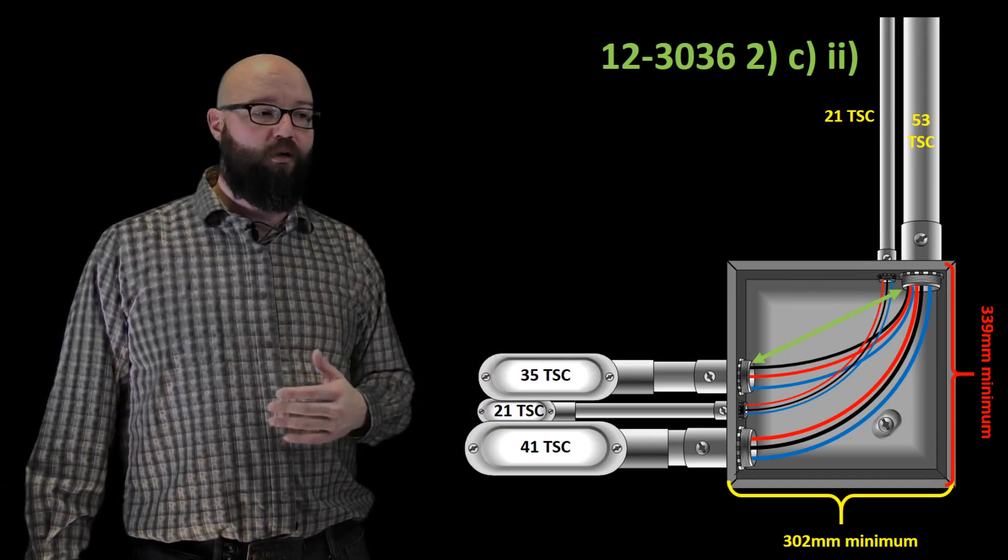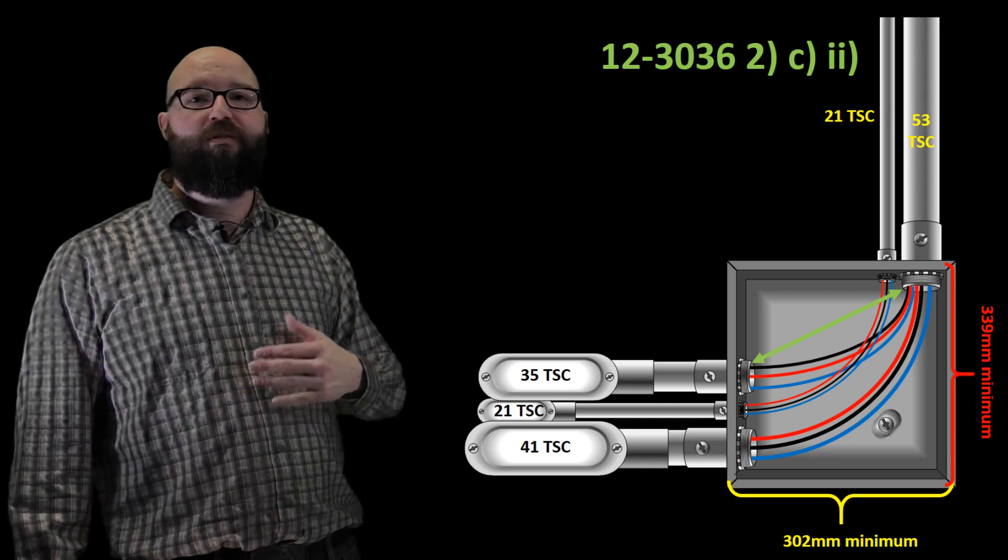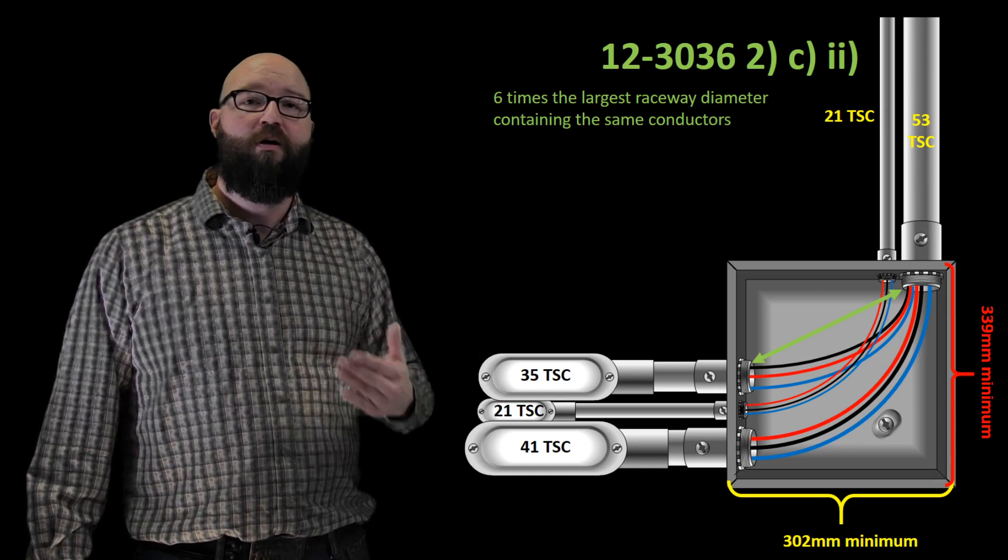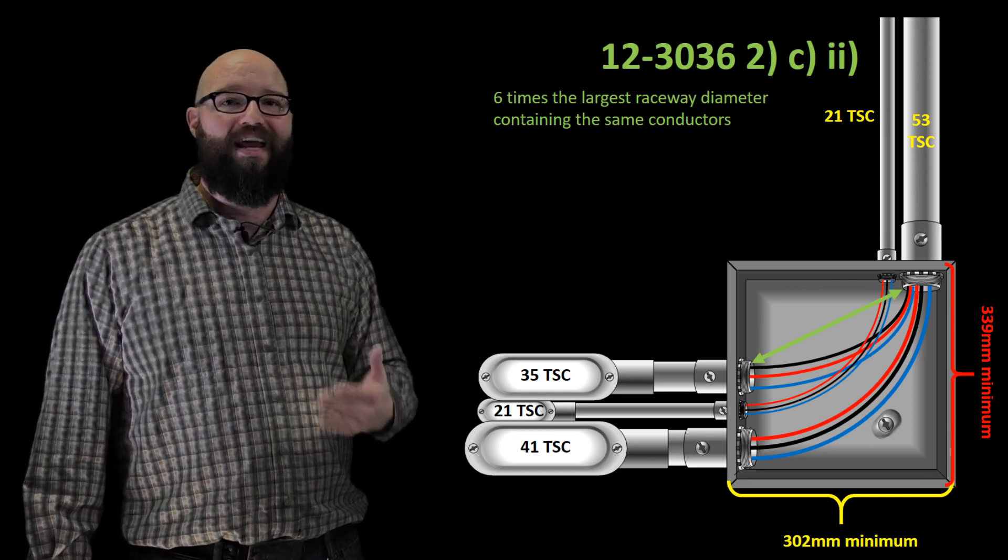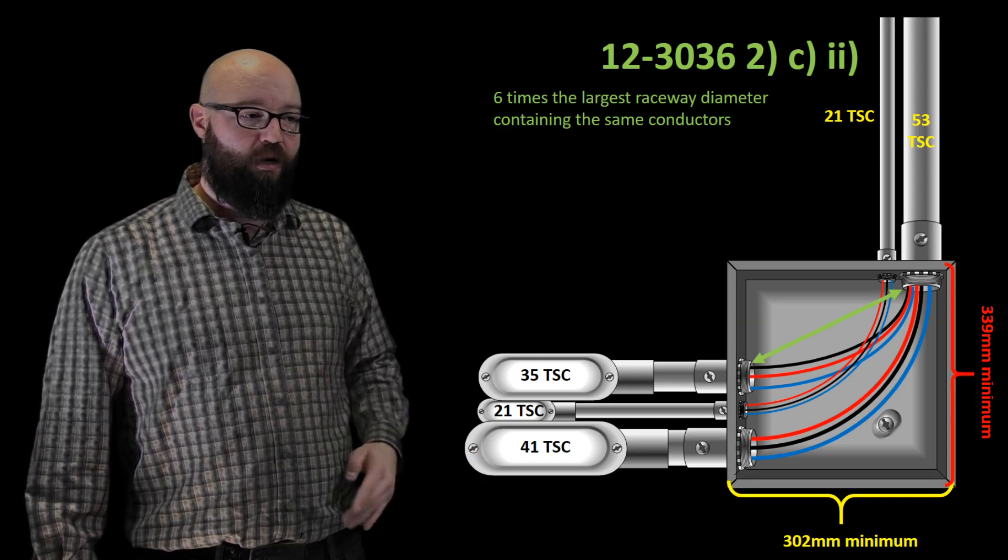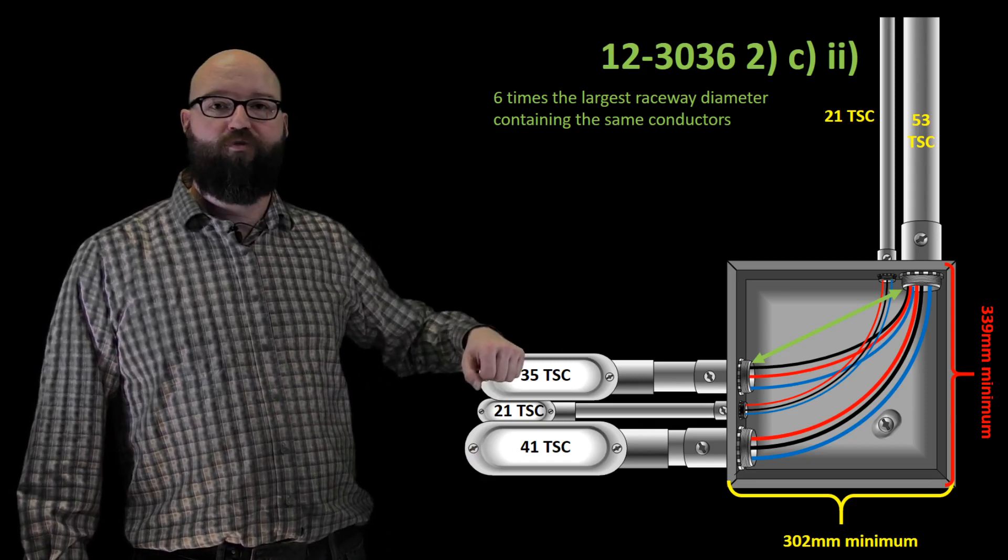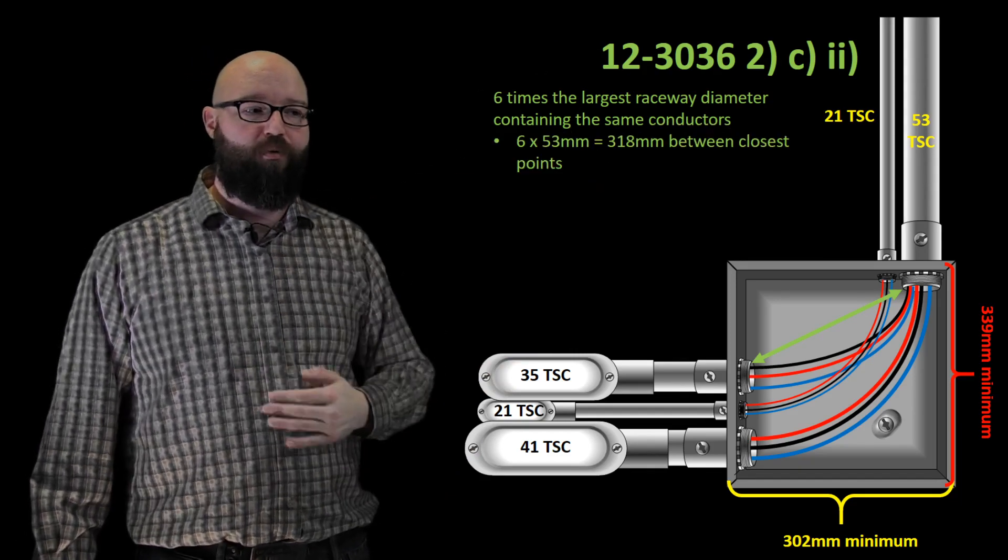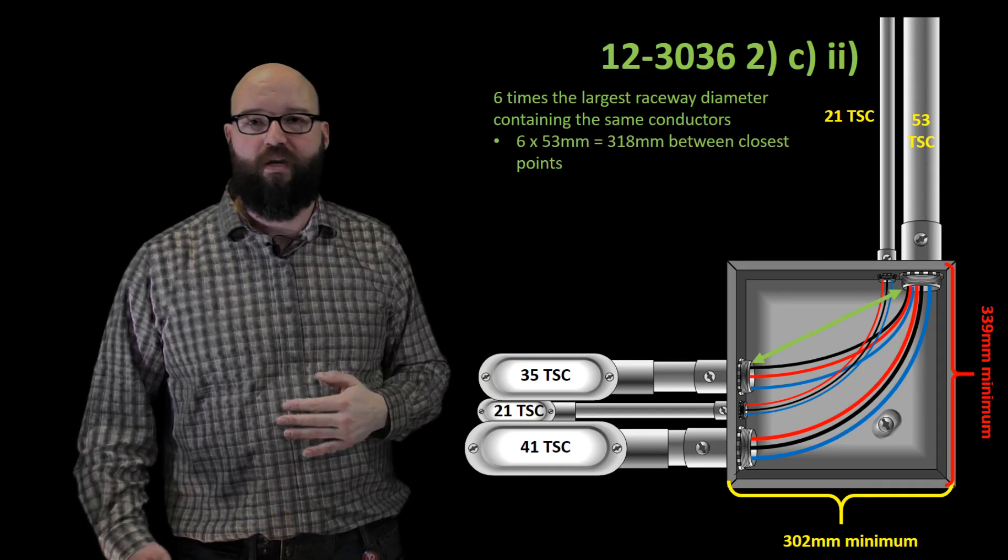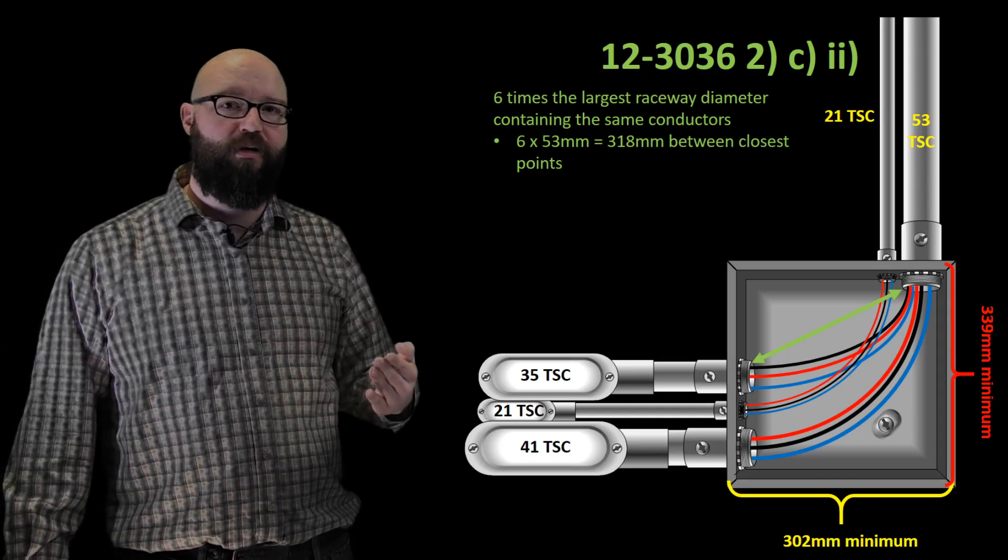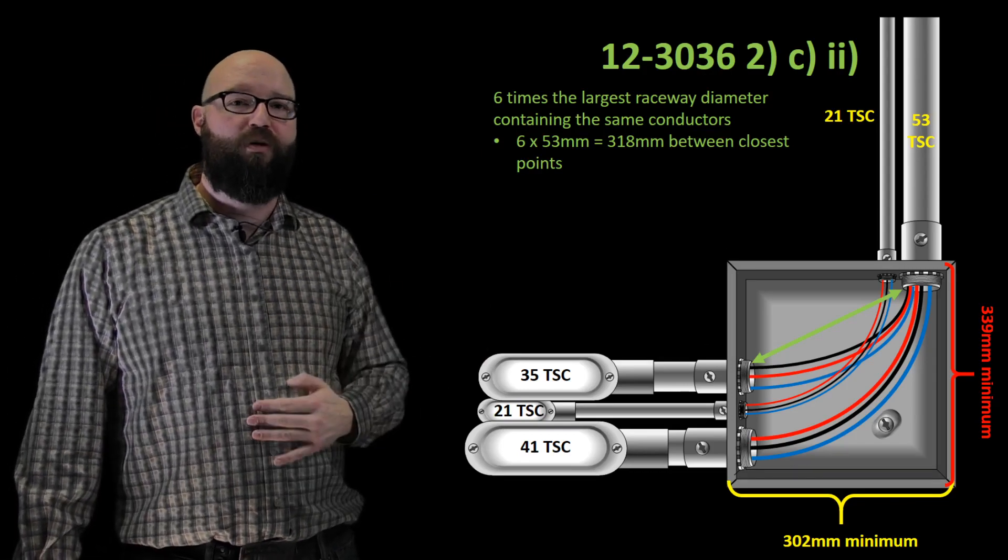If we take a look at 12-3036 sub rule 2 item C-II, it tells me all we're gonna do is take six times the trade size diameter of the largest raceway containing those conductors. So in this case, they are coming from our 35 trade size conduit and they go to our 53 trade size conduit. In this case, we would take the 53 trade size conduit as it's the larger, multiply it by six and we get that 318 millimeters. That's the minimum distance between those two conduits.